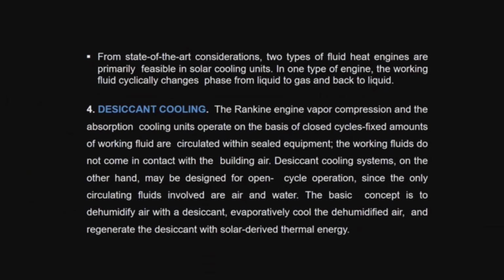From a state of the art consideration, two types of fluid heat engines are primarily feasible in solar cooling units. In one type of engine, the working fluid cyclically changes phase from a liquid to gas and back to liquid. The Rankine engine, vapor compression, and the absorption cooling unit operate on the basis of closed cycles. Fixed amounts of working fluid are circulated within sealed equipment. The working fluid does not come in contact with the building air.